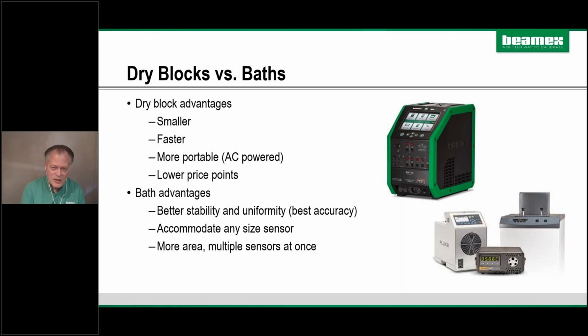A temperature bath, while it's slower, takes longer to get the media, typically silicone oil, to heat up. It does provide much better stability and uniformity. So, when you insert a probe into a dry block, the temperature is not the same at the top as it is down at the bottom, and you want the probe to be down at the bottom in a dry block. With a bath, you can put the sensor up high, or put it in the middle. It can be any kind of size, so there is a lot of flexibility there. And if you're looking for the best accuracy on a measurement, it's really the best way to go. So both have their place. But today we're going to be demonstrating a dry block to you guys.